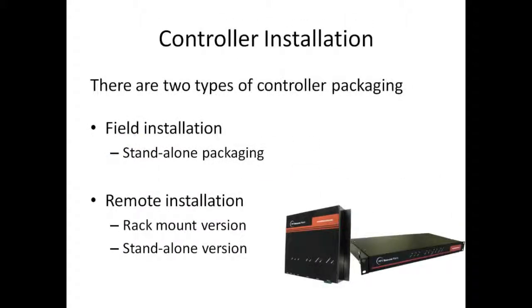Secure Point comes in 2 types of packaging. First of all, there's a standalone packaging that's primarily designed for field installation. Then there's a 19-inch rack mount version, which is designed for remote installations. Of course, you can still use the standalone packaging in a remote installation, for example, where you have a control room that doesn't have a rack.